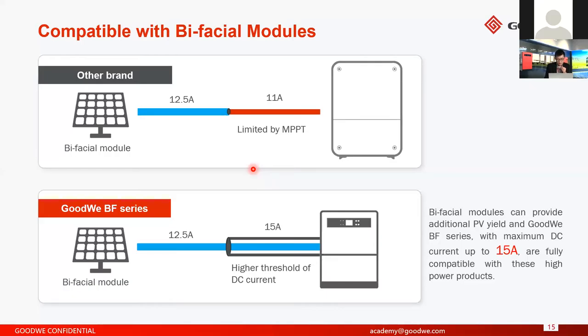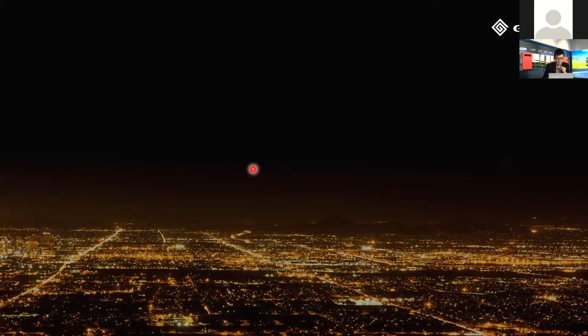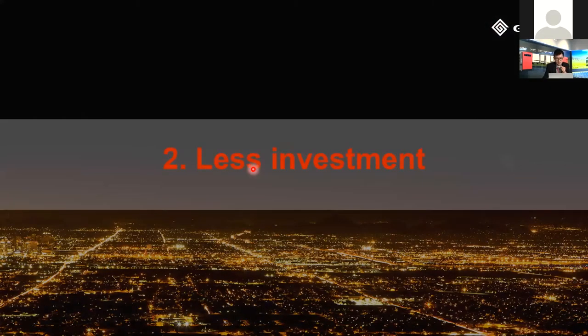But if you use a normal inverter to work with bifacial modules, the bifacial module current is 12.5 amps, but the inverter only accepts 11 amps. So the DC input current will be limited to 11 amps, and you will get power loss on the DC side. So that's a big loss, actually. So this part is about the less investment if you use GoodWe products. So let's check.